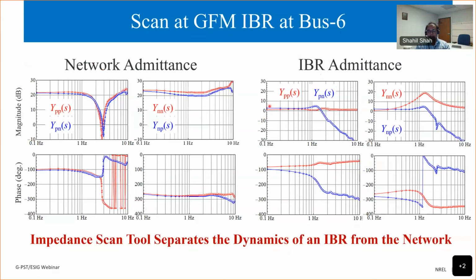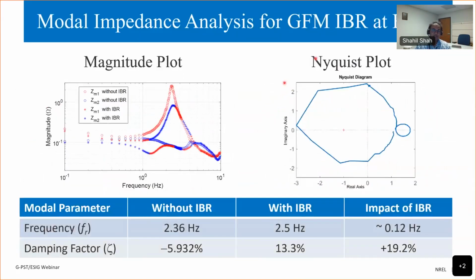The real strength of this tool is that by inserting that yellow box, it isolates the dynamics of that plant from the rest of the network. And that allows you to understand how this particular plant is impacting the stability. So by performing the scan and then post-processing the data, we get these admittance responses. Then we use those admittance responses to plot what are called modal impedances. The peak of the modal impedances will give you the resonance frequency, if there are any in the system, and the Q factor, or how peaky that resonance peak is, will tell you the damping.